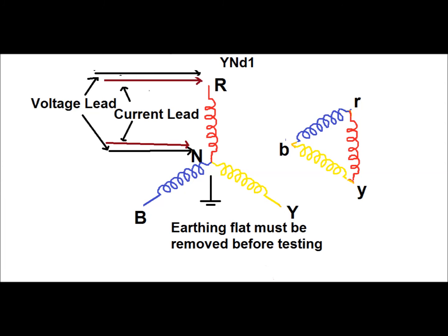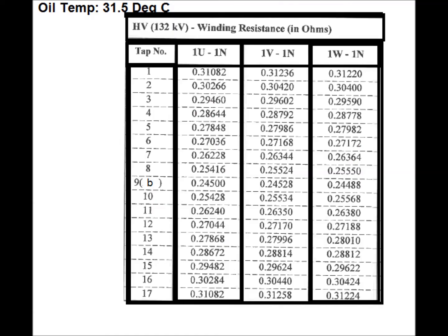Then in the test kit we have to select the proper current injection, which is normally set at 1 ampere and sometimes at 10 ampere. Then we turn the test current on and wait for the current to stabilize. When the current is stabilized, channel 1 or channel 2, as previously set, will show the resistance measured through the test kit. During the DC resistance test, we have to note down the oil temperature.